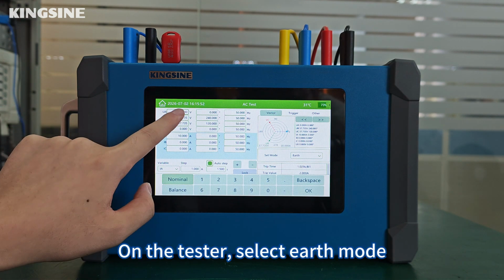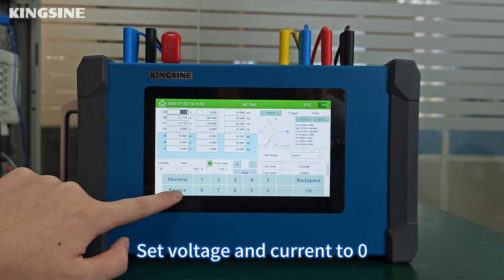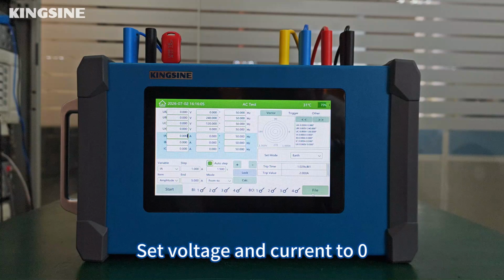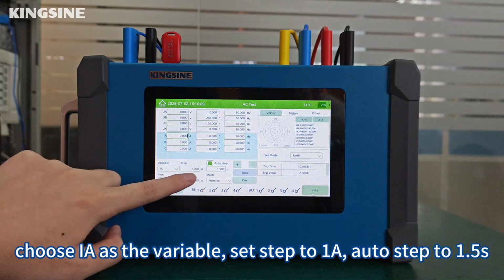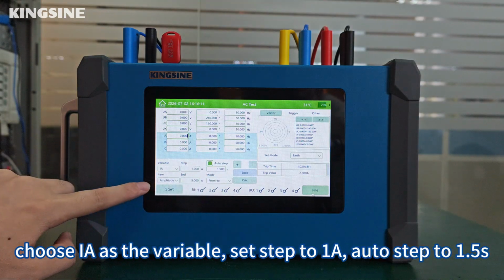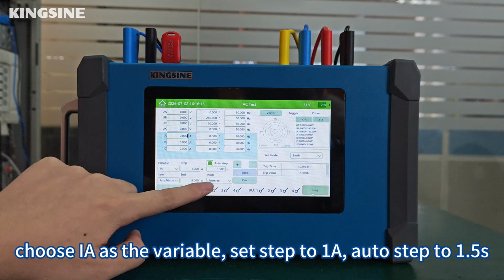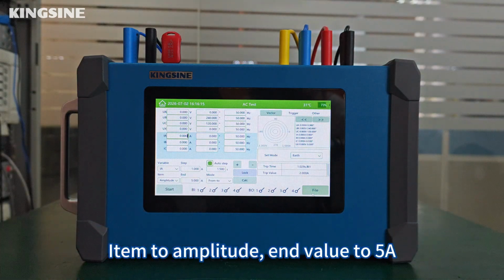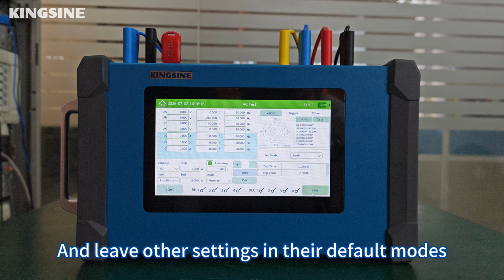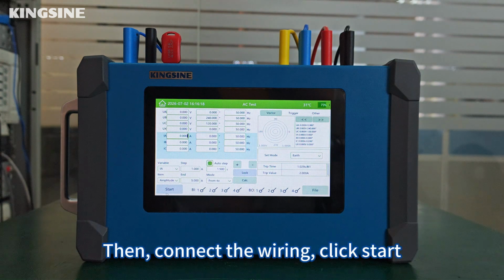On the tester, select earth mode, set voltage and current to 0. Choose IA as the variable, set step to 1 ampere, auto step to 1.5 seconds, item to amplitude, end value to 5 amperes. And leave other settings in their default modes. Then, connect the wiring, click Start.